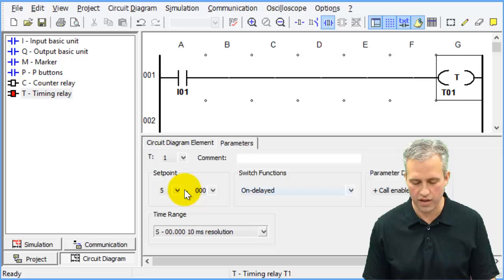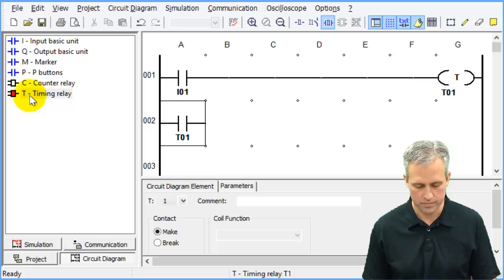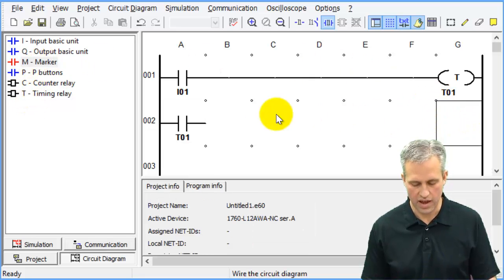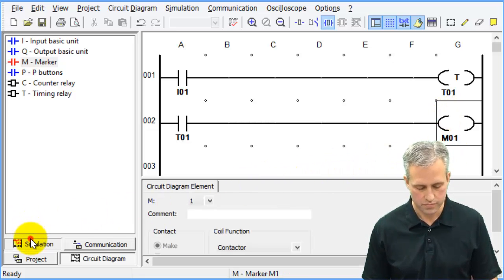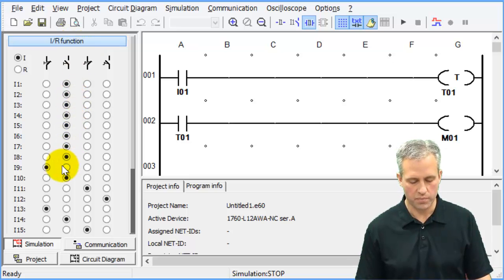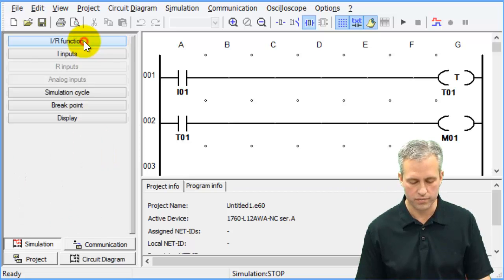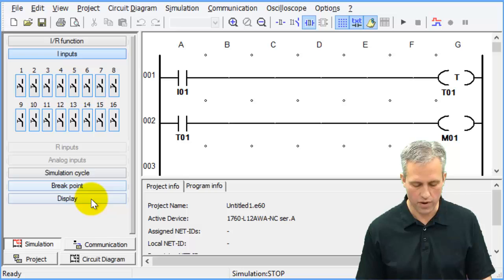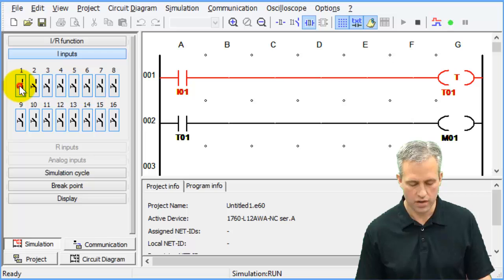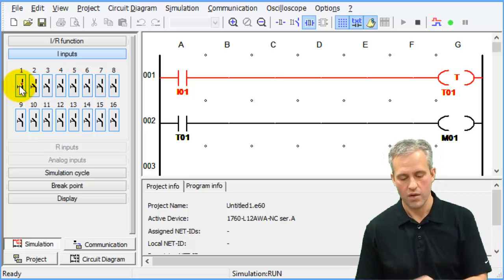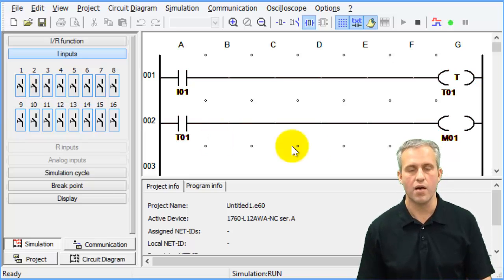So you've set on delay, five seconds, and it's going to control Marker 1. Let's go into the simulation. Make sure the push buttons are all the simplest type — normally open momentaries. Hit play, press I1, and the first rung goes high, but the second rung is not going high yet. Hold it down and — boom — there it went on after five seconds.